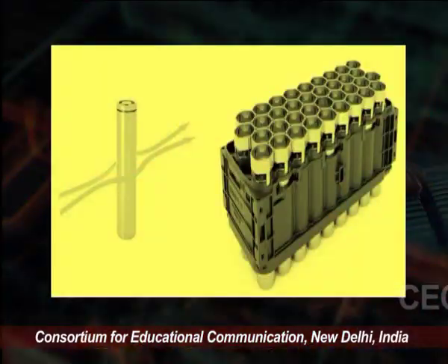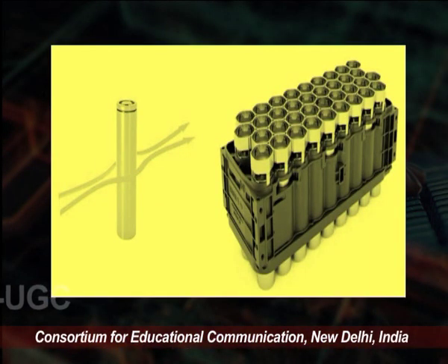Note that the coolant does not flow over either end of the cylindrical cell and hence does not cool the bus bar. You see on the screen here we have various cylindrical cells. They form the bus bar, which is immersed into the liquid, and they are connected with each other.